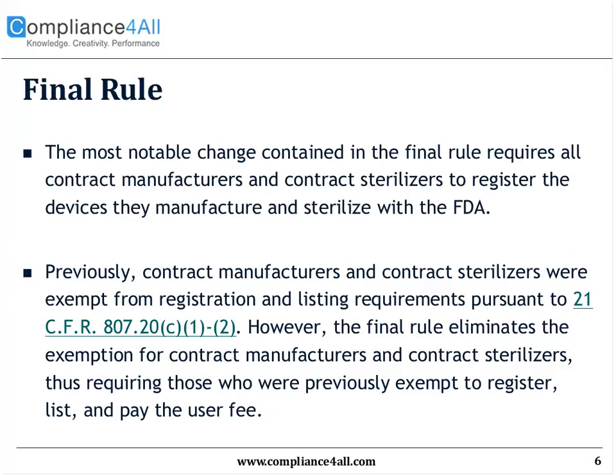The most notable change contained in the final rule requires all contract manufacturers and contract sterilizers to register the devices they manufacture and sterilize with the agency. Previously, contract manufacturers and contract sterilizers were exempt from registration and listing in accordance with 807.20 subpart C 1-2. However, effective immediately, the final rule does indeed eliminate the exemption for contract manufacturers and contract sterilizers, thus requiring those who were previously exempt to register, list, and pay the user fee.